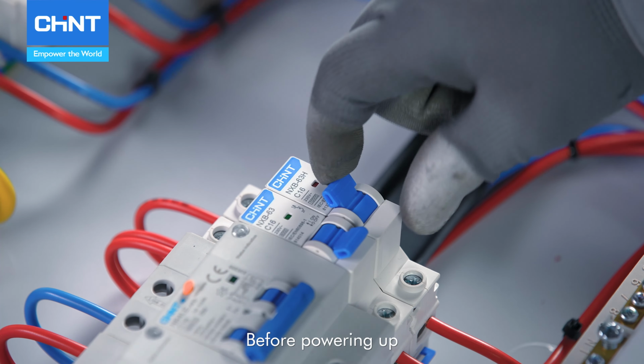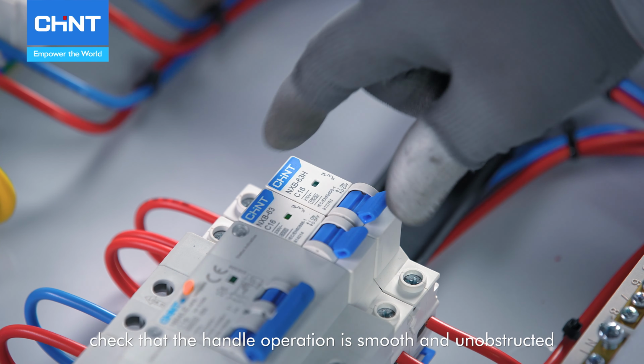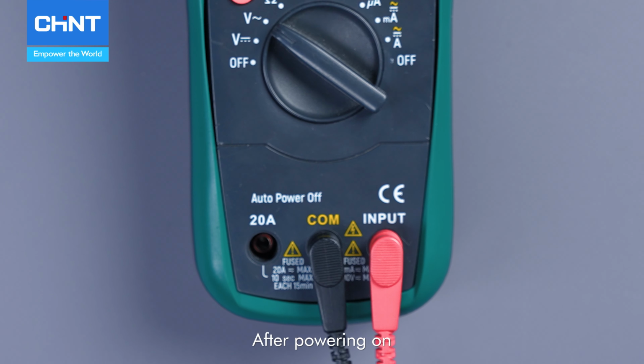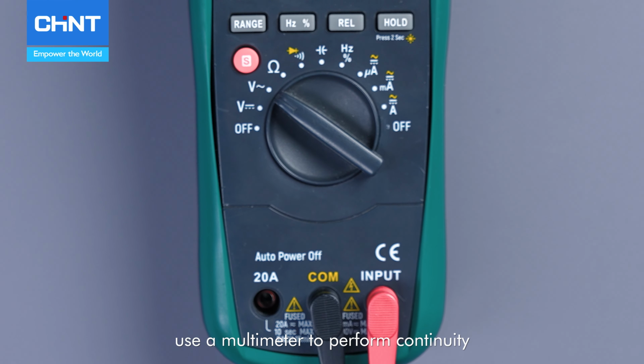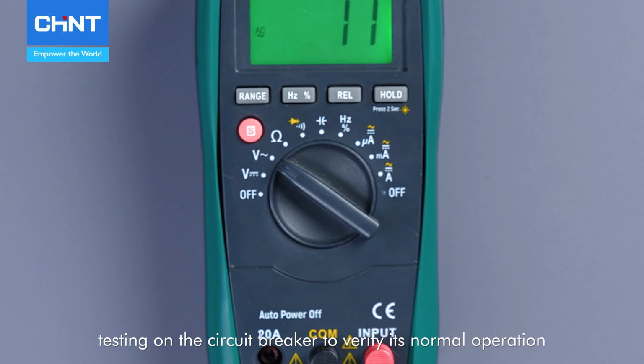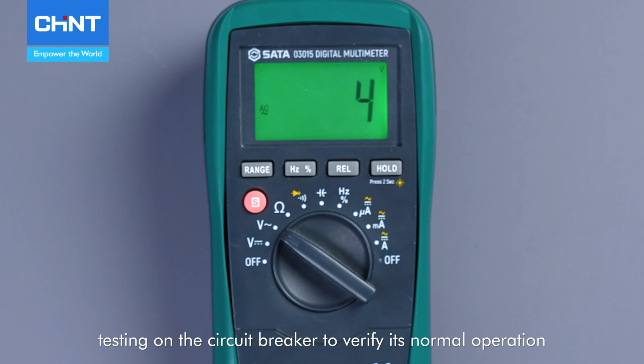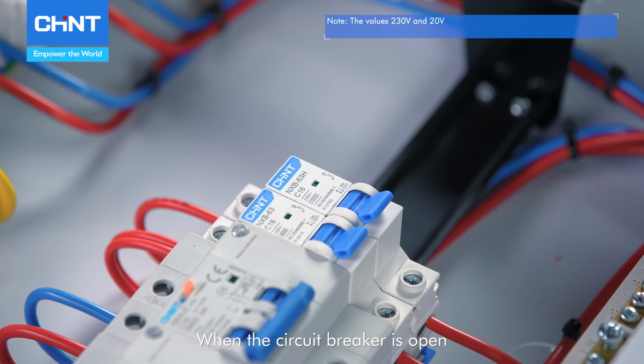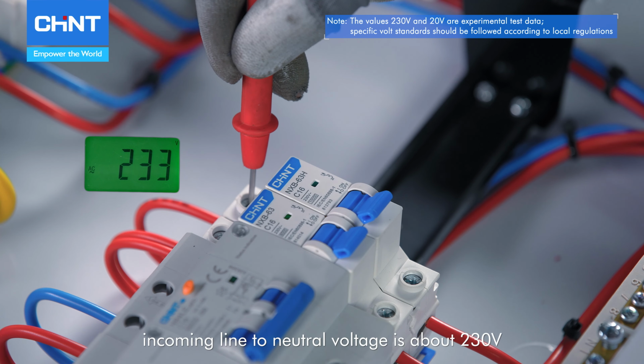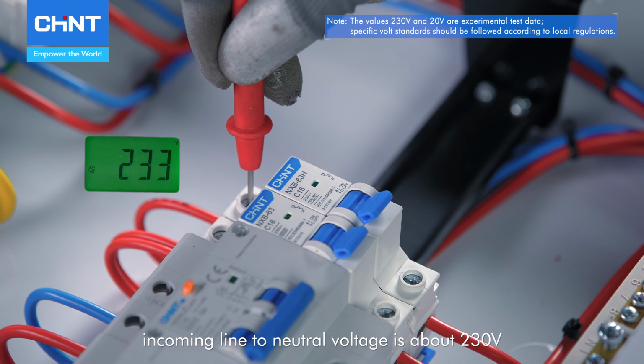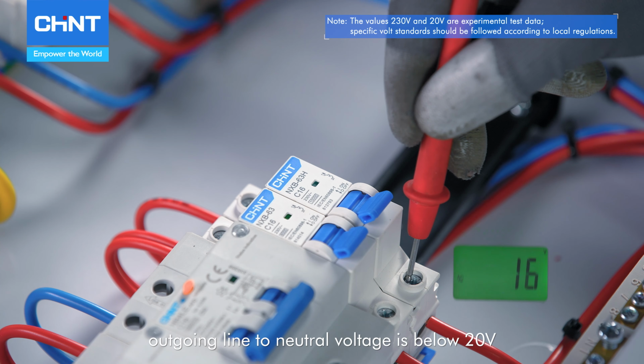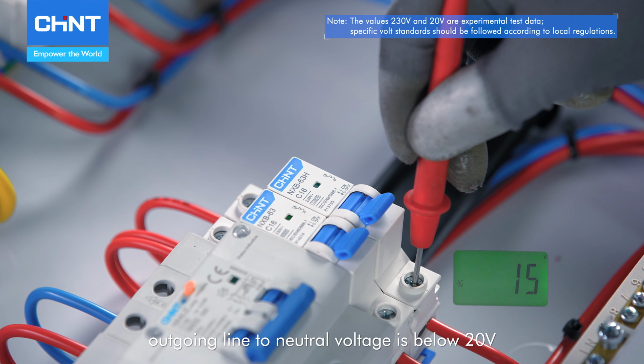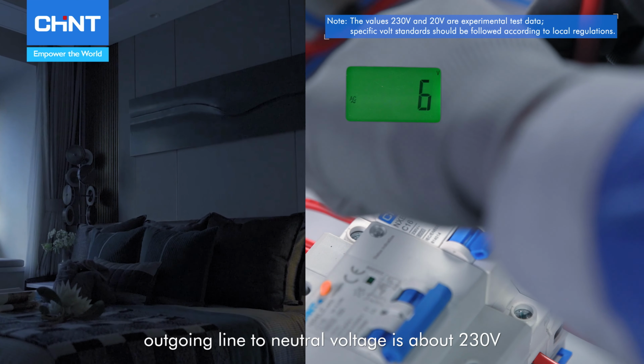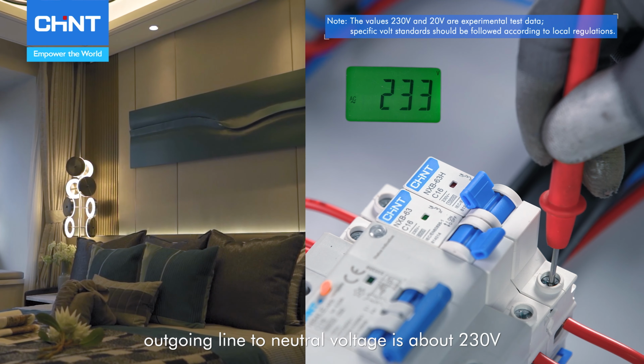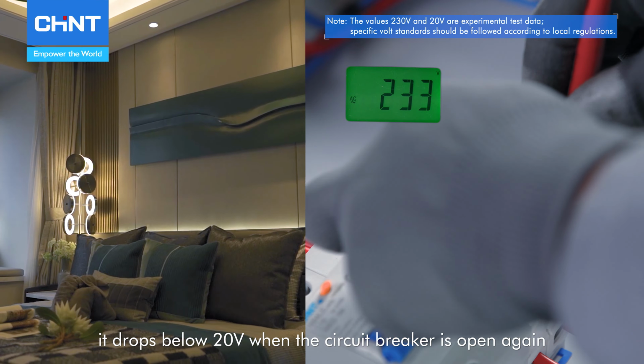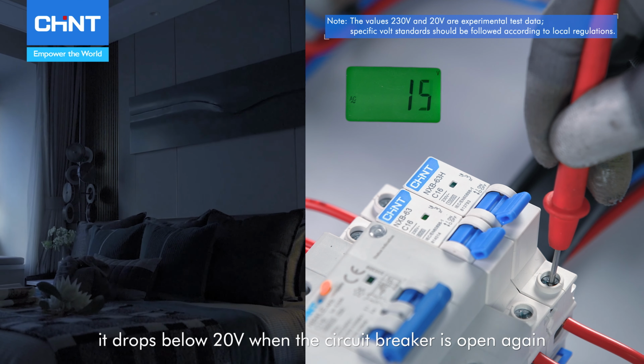Before powering up, check that the handle operation is smooth and unobstructed. After powering on, use a multimeter to perform continuity testing on the circuit breaker to verify its normal operation. When the circuit breaker is open, incoming line to neutral voltage is about 230 volts, outgoing line to neutral voltage is below 20 volts. When closed, outgoing line to neutral voltage is about 230 volts, and it drops below 20 volts when the circuit breaker is open again.